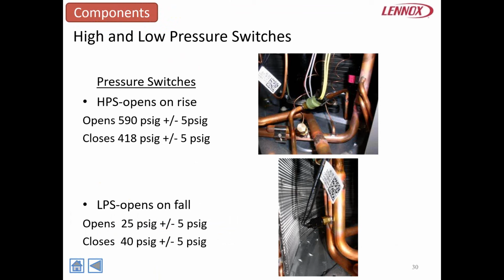On the low pressure side, it's very much the same thing. We open at 25 psi, and we close at 40 psi. So if we get down that low, there's something going on.